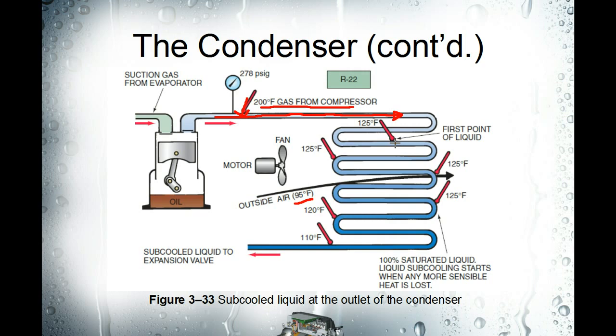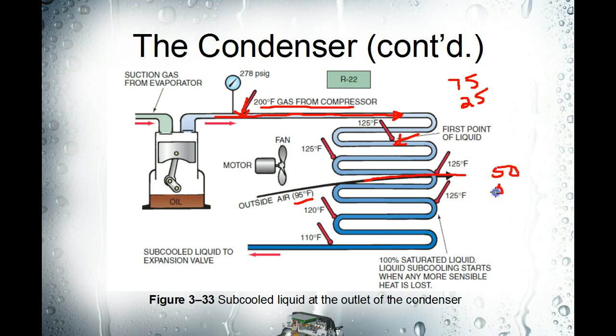The refrigerant will start changing state from gas to liquid. Just like in the evaporator coil, partway through the coil it's going to be 75 percent liquid and 25 percent vapor, and then theoretically halfway through it will be 50 percent vapor and 50 percent liquid. We're still saturated here — still on the pressure temperature chart. If you could measure each point of the condensing coil, you'd read 125 degrees, because as long as it's changing state at 278 psig it's always going to be 125 degrees.